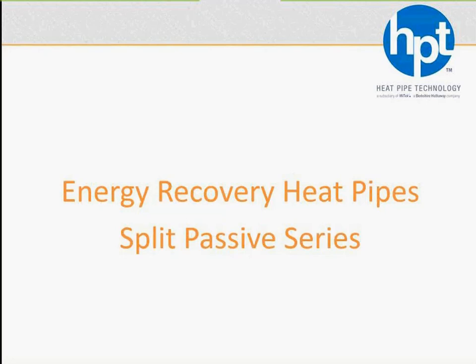Generally speaking, with heat pipes, you really don't have a lot of moving parts. If any, you've got the refrigerant flowing from one side to the next. If you have valves on them, the valves are typically not your typical solenoids that are on and off 100 times a day. Those are on some mornings, off evenings, perhaps. So little maintenance is actually required if you happen to have valves in your systems. But most of the heat pipes that we put out there need little maintenance. Our IOM, if you care, we'd be more than happy to send that to you. You can take a look at what's required for those products. But generally, minimal maintenance is required.